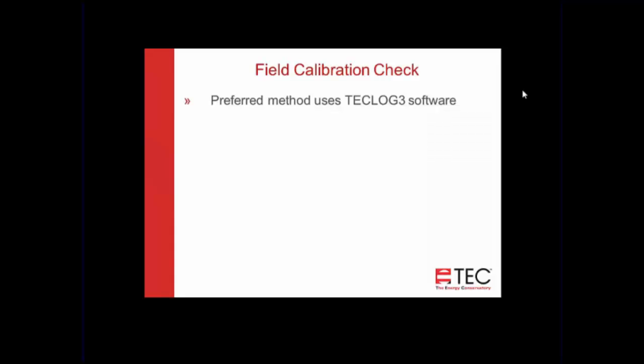A preferred method that we're strongly suggesting is to use the TECLOG3 software to do this check. So then you've got documentation instead of having paper documentation. You've got a live graph with numbers, and you can set an averaging period and get rock solid data and have very well documented proof that you did the test. And some advantages of that is the software recognizes the serial numbers, because there's a chip in the gauges that the software recognizes, and it brings in that information, and it also brings in the last date of factory calibration.